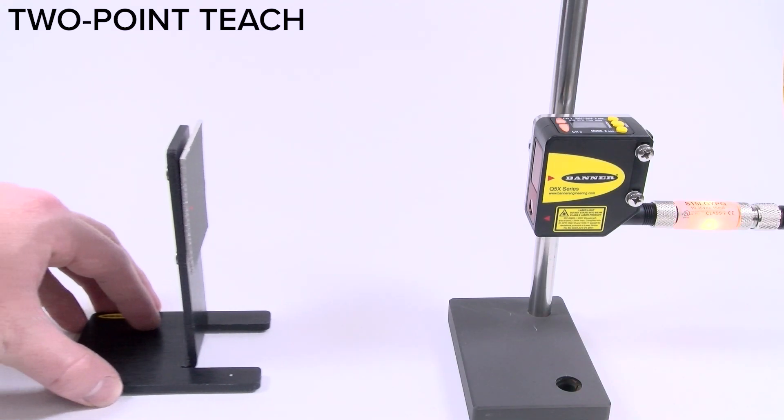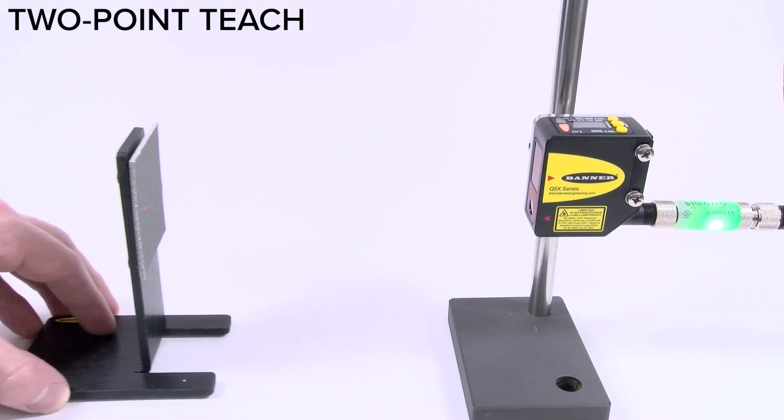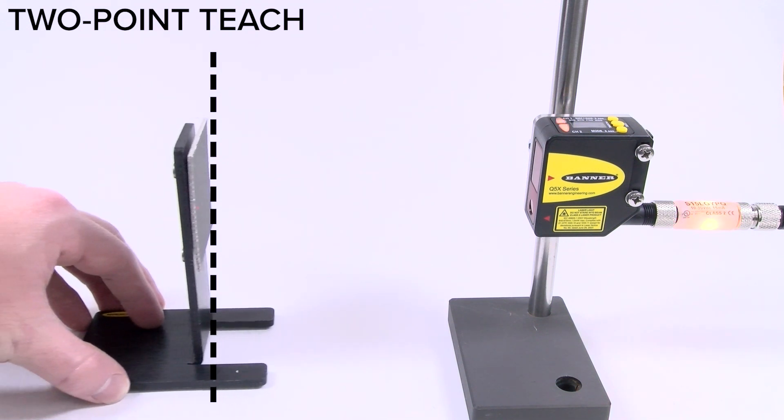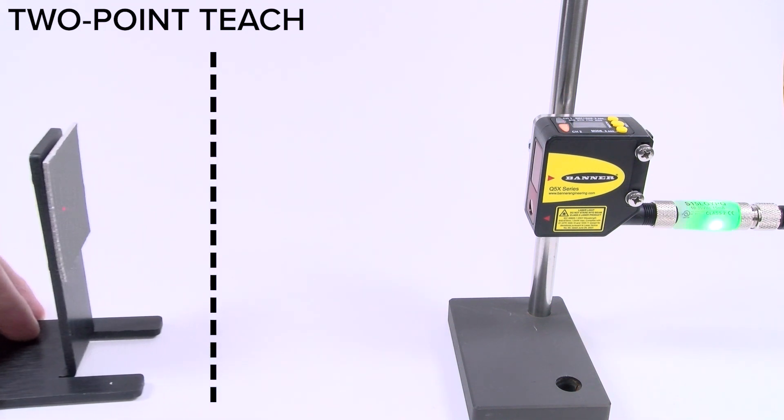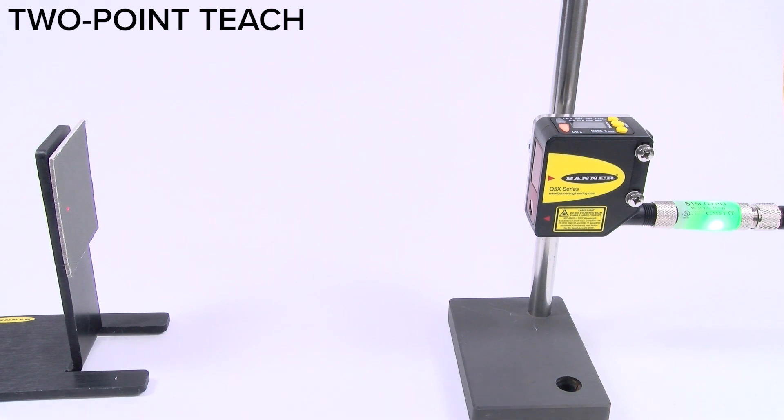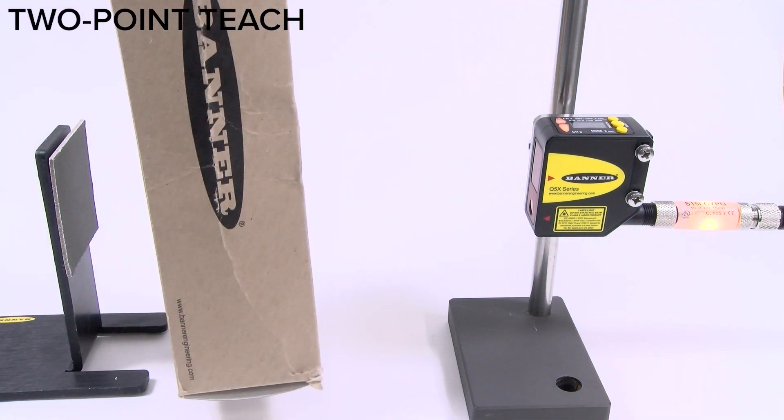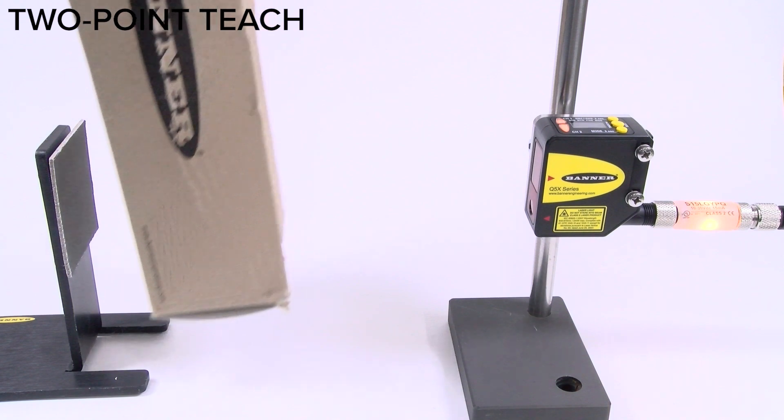The most common teach mode for the Q5X is 2-point teach. This mode will be able to solve most applications and is generally used when there is a background with an object passing in front. After being taught, the sensor will ignore the background and detect the object.